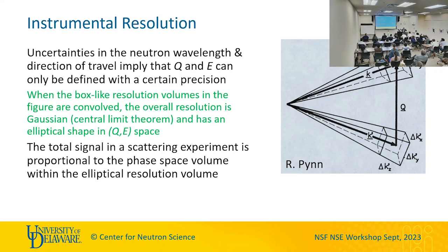That means you will have a smaller and smaller detection count rate. There is essentially a theorem that limits the count rate of your instrument depending on the resolution. And spin echo is the way we break out of this, because if the count rate is too low, the experiment becomes impossible.